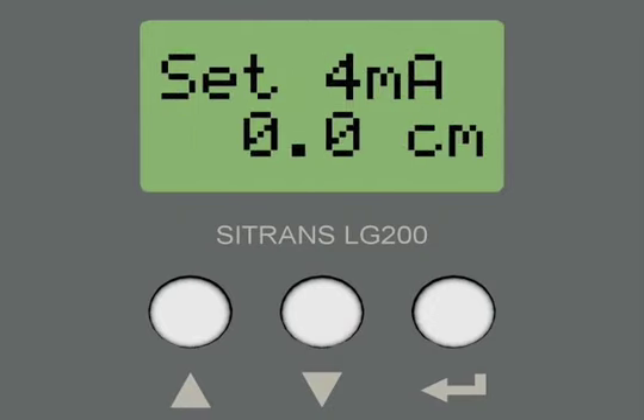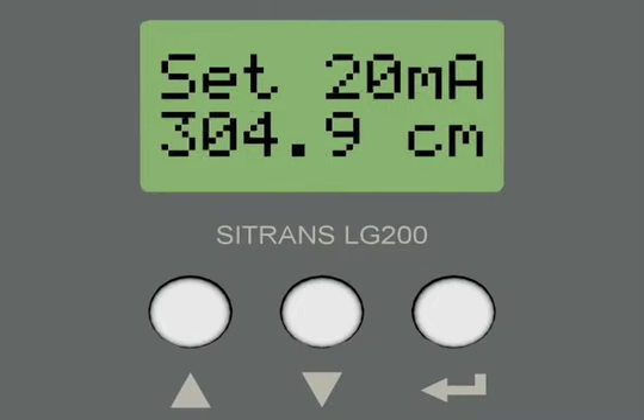The final 2 parameters to set are the 4 milliamp and 20 milliamp set points. The 4 milliamp set point parameter has a default value of 0. This represents the bottom of the probe and the minimum liquid level. The default value of 0 is what we want for our application, so we can push the down arrow key to advance to the 20 milliamp set point parameter. The 20 milliamp set point represents the maximum liquid level under normal operating conditions. In our application, we will set this value to be 55 centimeters.